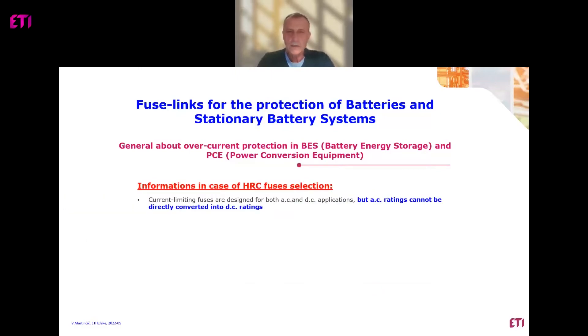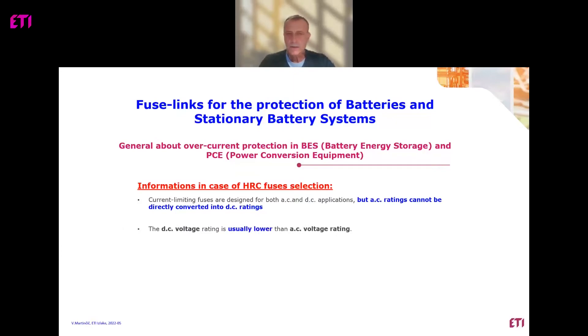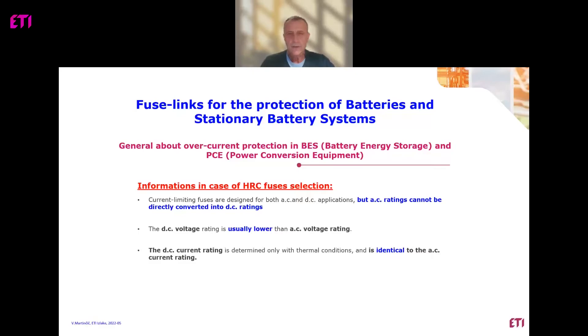There is some important information regarding high rupturing current fuse selection. Usually, current limiting fuses are designed for both DC and AC voltages, but AC ratings cannot be directly converted into DC ratings. This means that the AC voltage rating of a fuse is not comparable with the DC voltage rating of the same fuse — DC voltage is usually lower than AC voltage. Regarding current, the DC rated current is usually identical to the AC current of the same fuse, so there are no changes there.